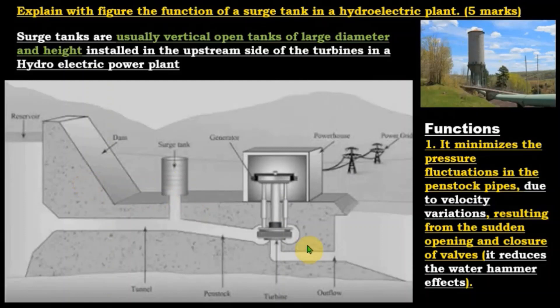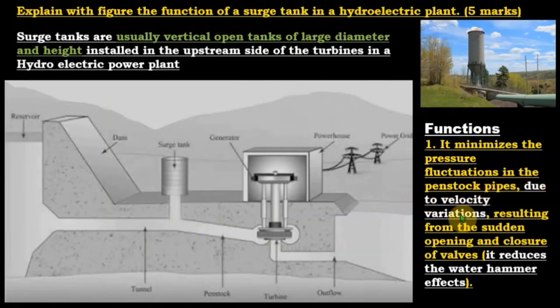The surge tank functions to dampen out pressure waves or pressure pulsations in the pipeline. It minimizes pressure fluctuations in the penstock pipes due to velocity variations resulting from the sudden opening and closure of valves — that is, it reduces the water hammer effects.